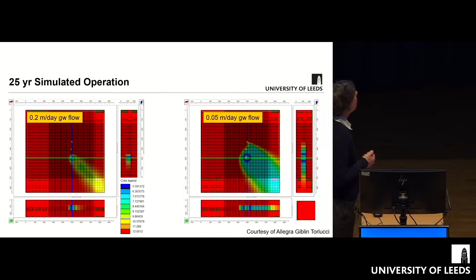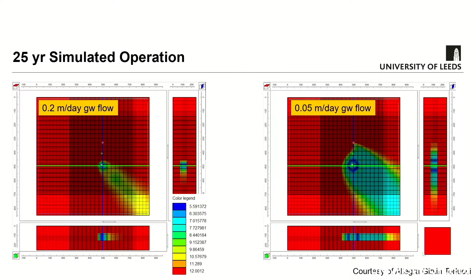In the high groundwater scenario on the left, here is where we're taking out water at 12 degrees. We are developing a cool plume going downstream. Here, when we have lesser groundwater flow, we still have a cool plume going downstream, but this is our second well, and because conduction is more important relative to convection, we're potentially moving towards thermal breakthrough to that well in 25 years. So there's a couple of points that come out of that. Having high groundwater flow helps us provide a high heat demand. It reduces our risk of thermal breakthrough between our wells, but it creates a downstream cool plume.